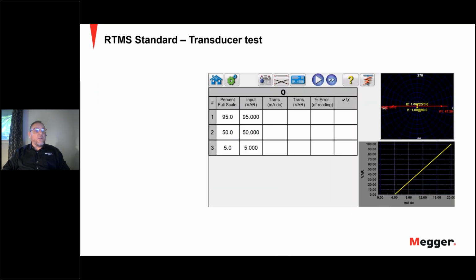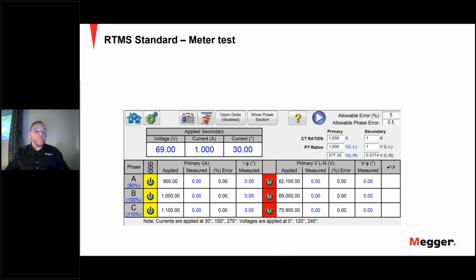Then we've got the transducer test, which I covered a little bit. In conjunction with the transducer hardware option in the SMRT, the transducer test provides a quick approach to testing all types of single-phase and three-phase electrical transducers. The meter test provides a quick and easy approach to testing the metering function of protection relays. The user will simply select the output channel, similar to the manual vector screen, and the values will be in secondary, default or primary by clicking on the different ratios.